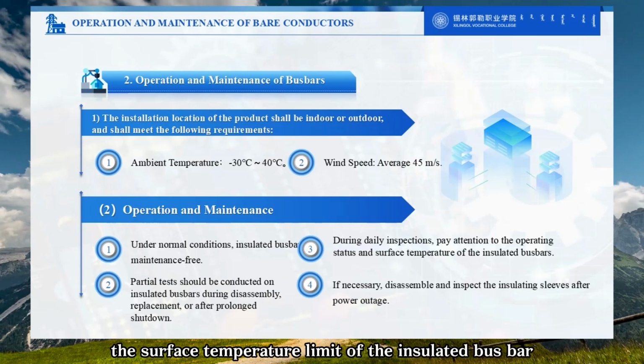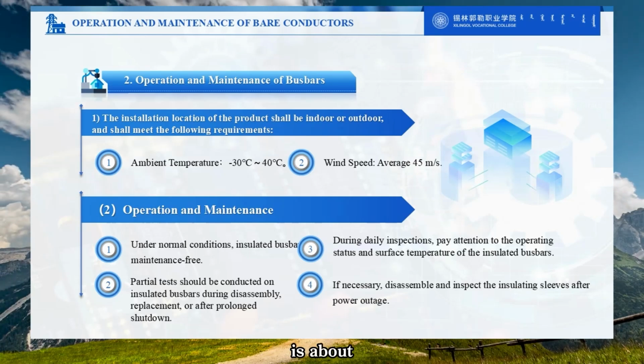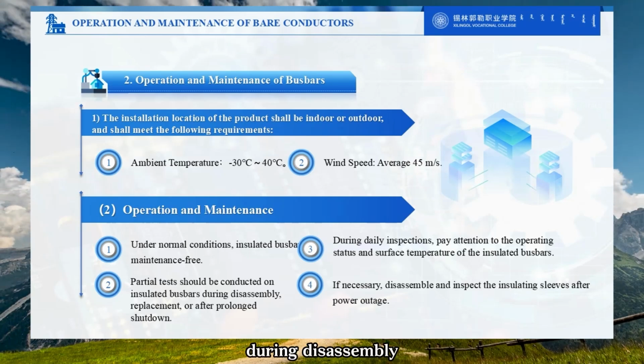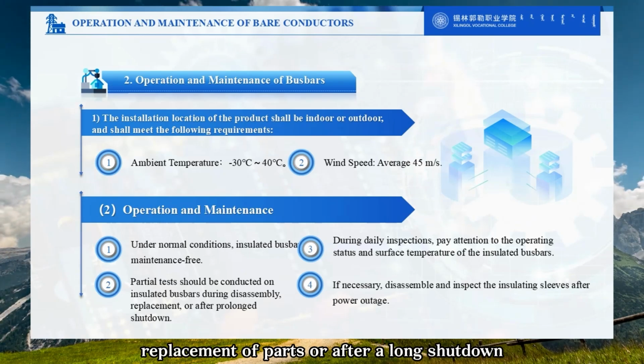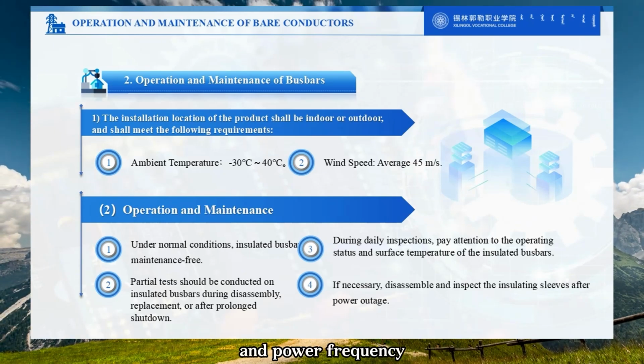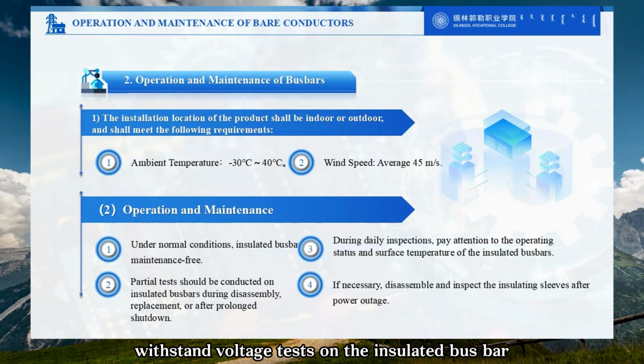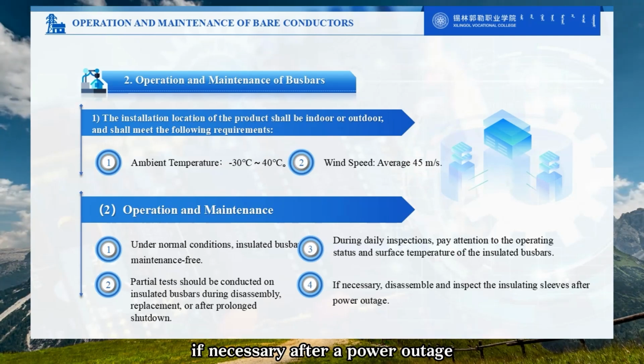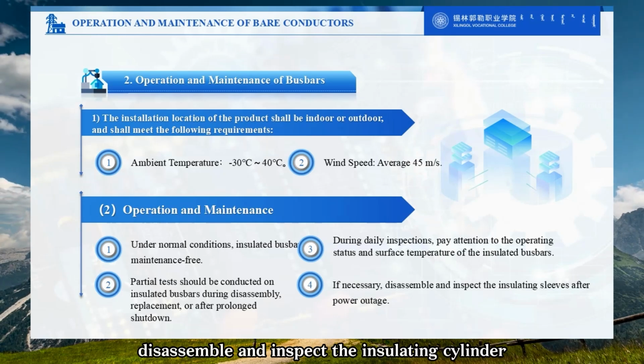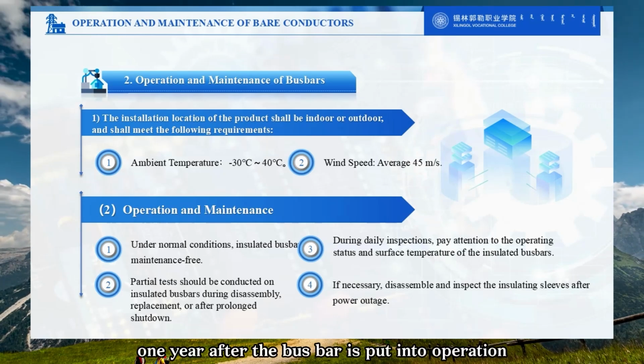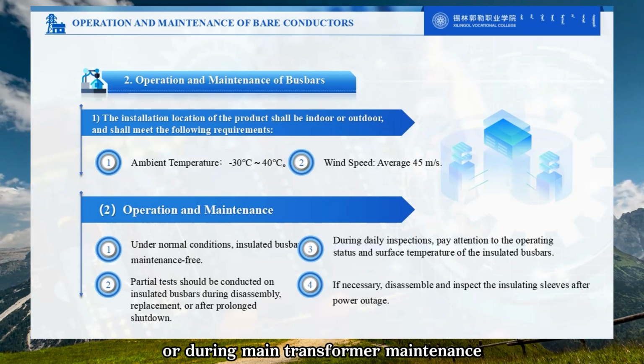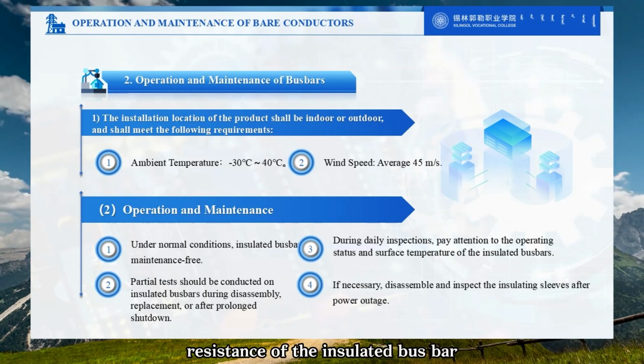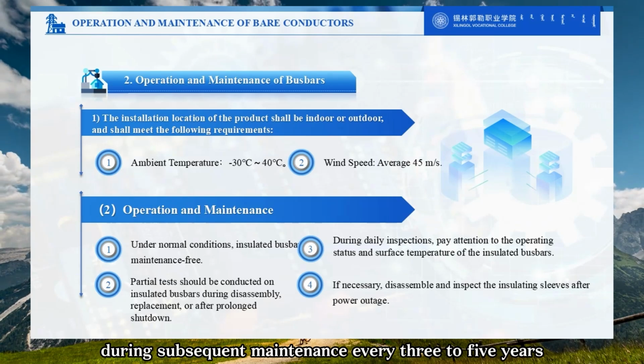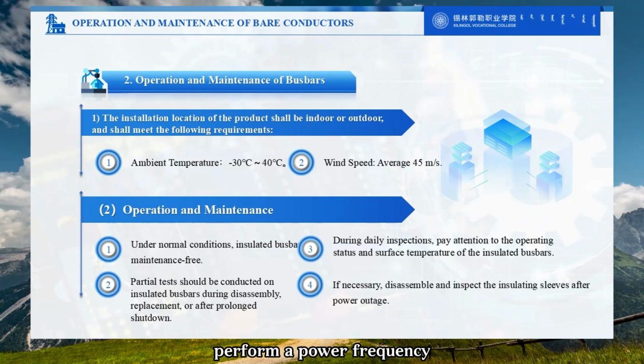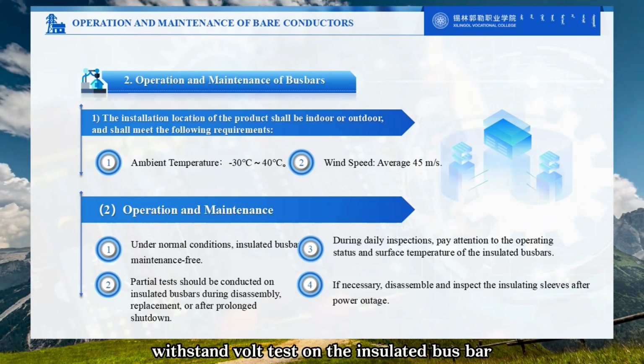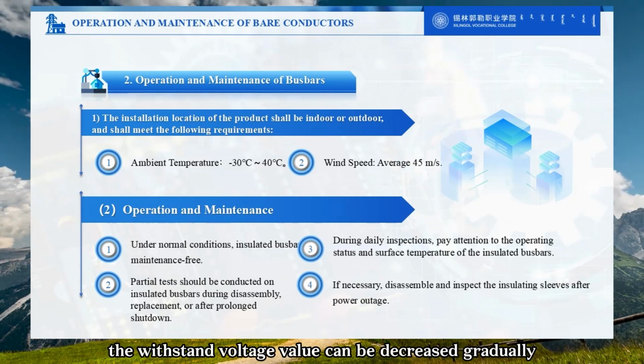Under rated current, the surface temperature limit of the insulated busbar is about 65 degrees Celsius. During disassembly, replacement of parts, or after a long shutdown, perform insulation resistance and power frequency withstand voltage tests on the insulated busbar. If necessary, after a power outage, disassemble and inspect the insulating cylinder. One year after the busbar is put into operation or during main transformer maintenance, measure the insulation resistance of the insulated busbar at any time. During subsequent maintenance every 3 to 5 years, perform a power frequency withstand voltage test on the insulated busbar. The withstand voltage value can be decreased gradually.